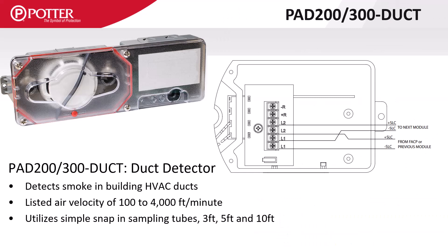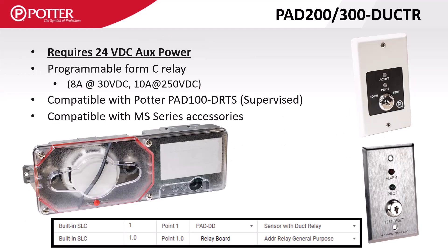Potter offers two models of duct detector. The PAD Duct is a simple SLC duct detector; the housing does not include a built-in relay, and there is no remote test station compatible with this detector. The PAD Duct-R does have a built-in relay, but it also requires 24 volts auxiliary power due to the higher amperage relay and the ability to have either a PAD DRTS or an MS Series remote test switch wired directly to the detector.